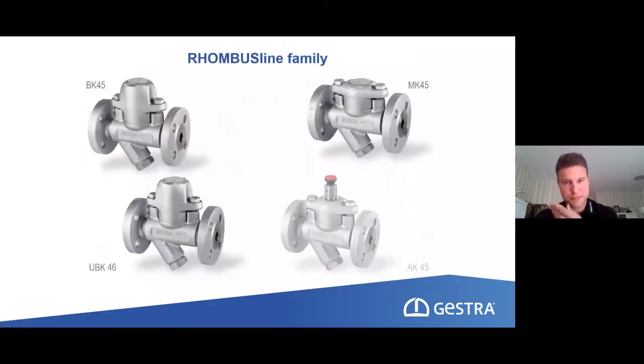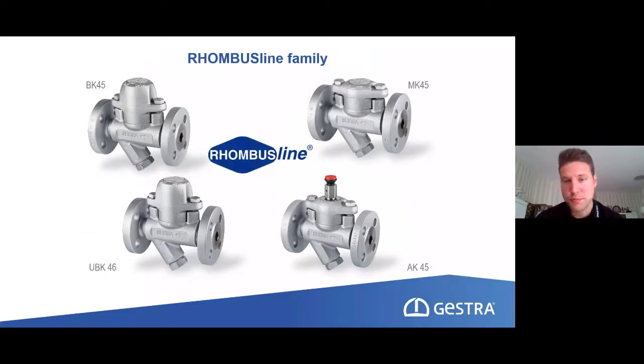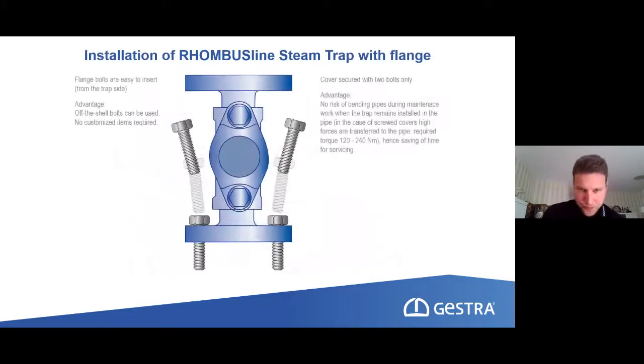Okay, so that was it so far for the ball float steam trap, but we also want to take a look at the other ones. If we take a look at this kind of steam trap we are seeing right now, we see a very specific design. All of them are rhombic in shape, and this is what gives us the information. This is why we had to design it that way, because of the easy installation requirement we spoke about earlier. And here we can see different kinds of steam trap. The thermostatic ones have this very specific design nowadays, and we want to go into more detail on these steam traps.